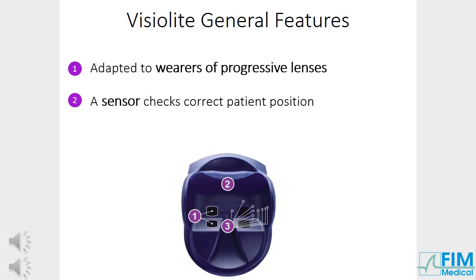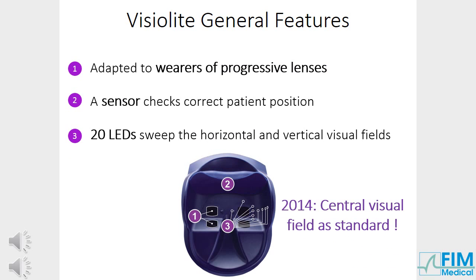A sensor checks correct patient position. The test lights up if the position is correct; on the computerised model, this is indicated on the screen. Correct position is required to perform tests with accurate results. To test peripheral vision, the Visiolite mask uses 20 LEDs which sweep the horizontal and vertical fields.